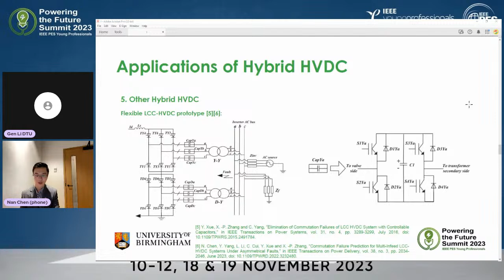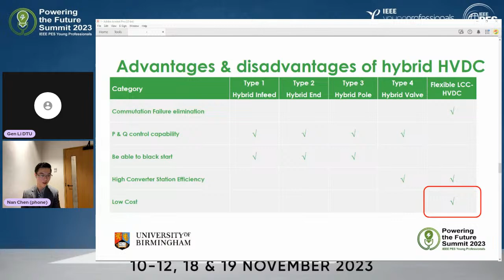So basically, I will give a summary of the advantages and also disadvantages of hybrid HVDC. I will talk about 5 aspects, including the commutation failure elimination ability, the active power and reactive power control capability, whether it can black start, the efficiency of the converter station, and the economic performance, for example, whether it has low cost. From the comparison, you can find that the flexible LCC HVDC proposed by Birmingham has the benefit of eliminating commutation failure, has low cost and high converter station efficiency. Then in the next part, I will go into some more details about the economic performance of the flexible LCC HVDC. Next page, please.